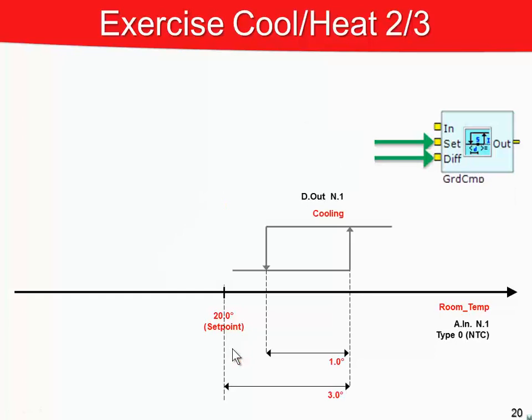While these are the specifications of the current exercise. There are three and not two operating parameters. The set point is available also here, but it is no longer in the center of the stage, but on the left of the stage. And the on and the off of the stage are relative values defined by an offset of 3 degrees and a differential of 1 degree.